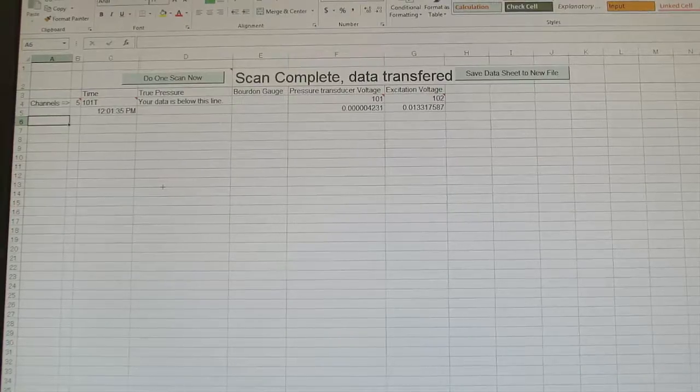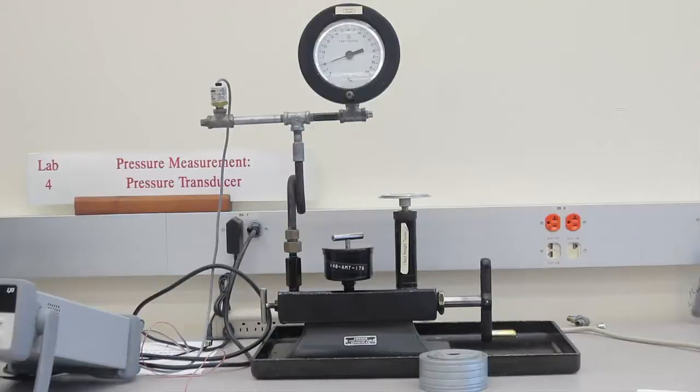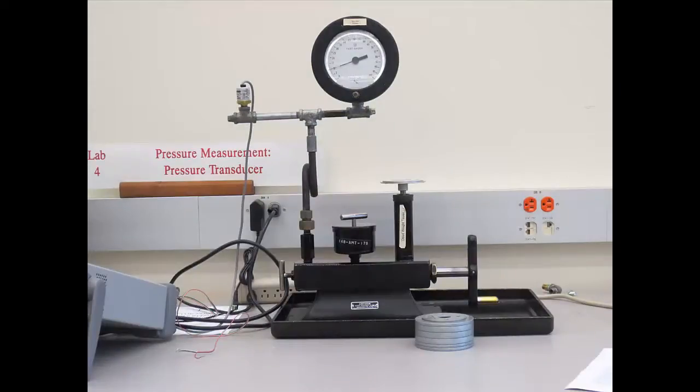Now we are ready to calibrate the pressure transducer and the Bourdon tube gauge. To proceed with the experiment, you will add the weights in 10-pound intervals so you can calibrate the pressure transducer and the Bourdon tube gauge. You will go up to 100 pounds and back down to 10 pounds.